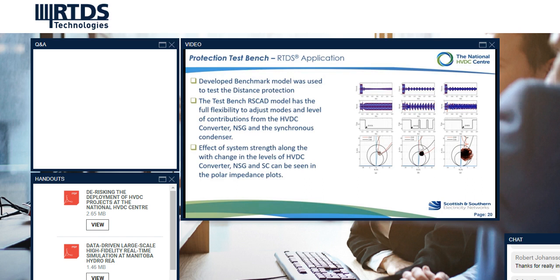This change in behavior would cause various critical challenges for the distance protection relay. These challenges can be slower detection of fault, detection of fault in the wrong zone, or not detecting the fault at all. Similar scenarios can be simulated and studied to de-risk the future integration of HVDC and non-synchronous generation in the GB network, thus de-risking the future integration of any HVDC project.